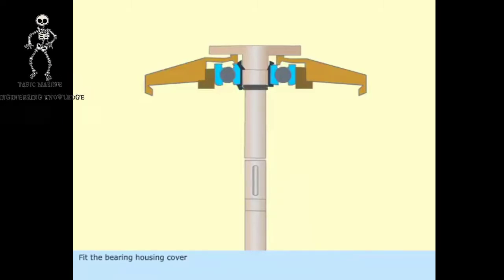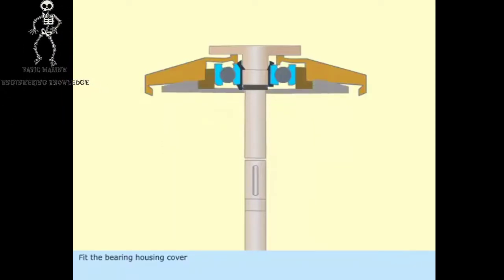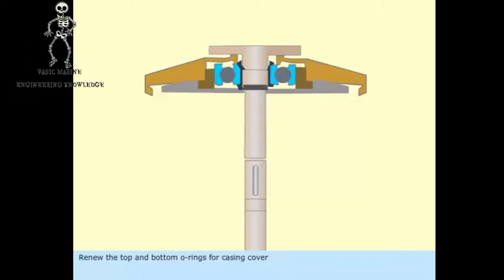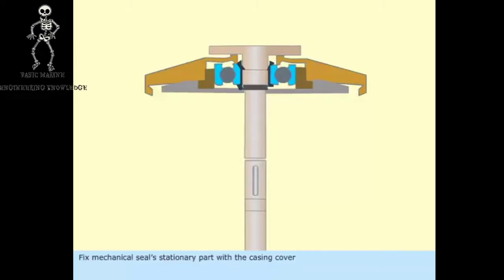Fit the bearing housing cover. Renew the top and bottom O-rings for casing cover. Fix mechanical seal's stationary part with the casing cover.